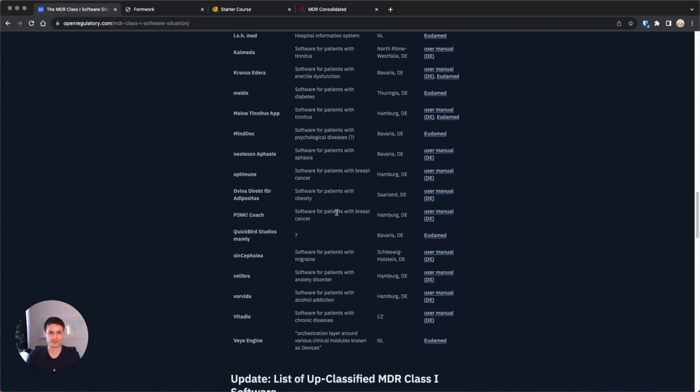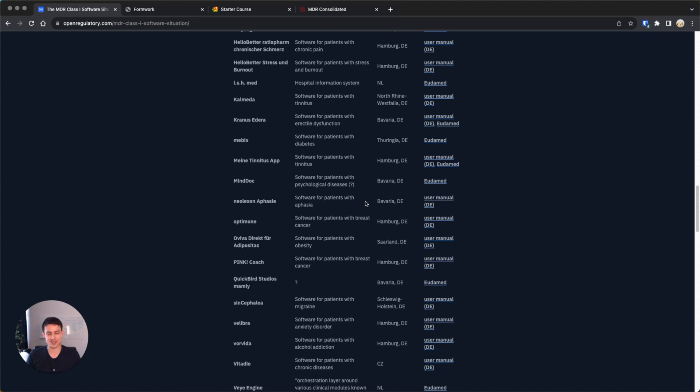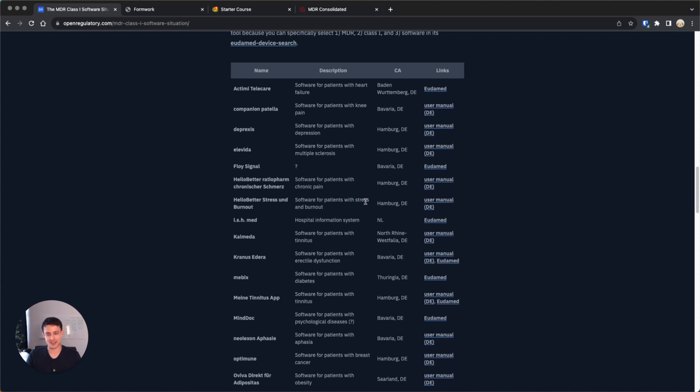That's where it gets super messy. And that's actually the essence of this example where we gathered all these class 1 devices. If you search for class 1 software situation, you find this table of different class 1 devices and in which countries they actually are. Because it's so unclear, different competent authorities, different state authorities who are responsible for class 1 monitoring, they come up with their very own subjective interpretations of what a class 1 device is.